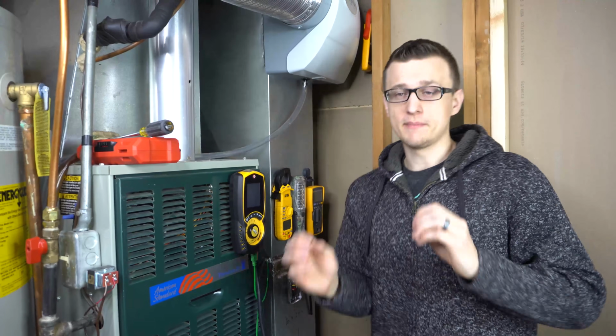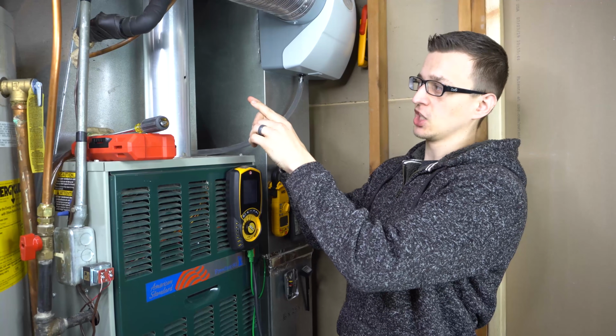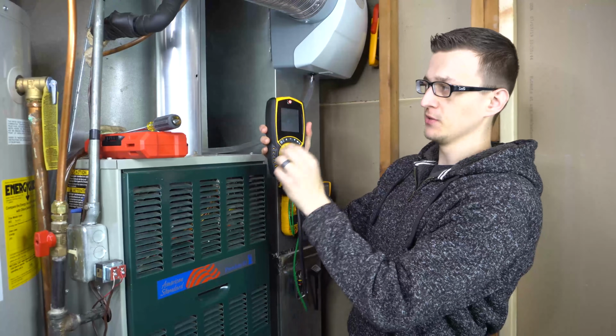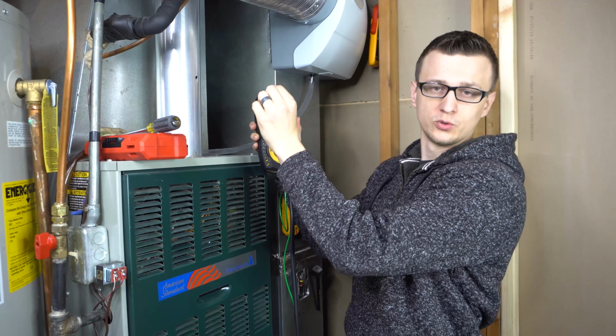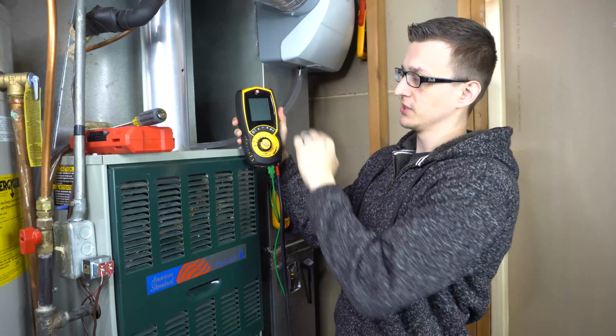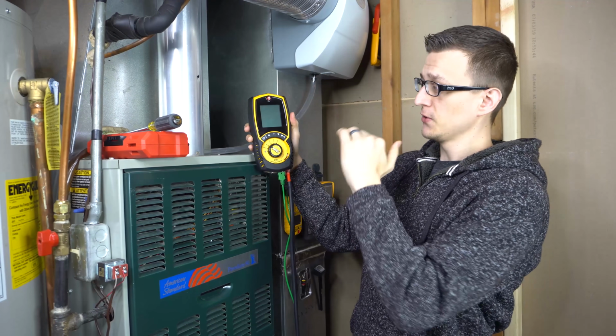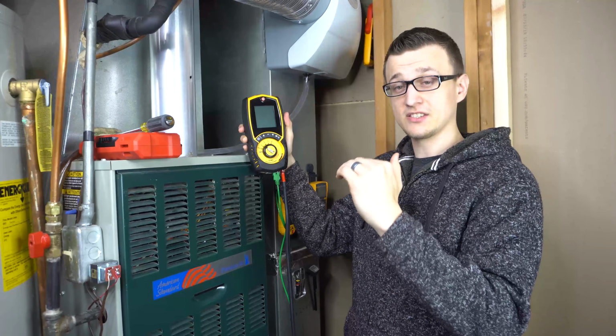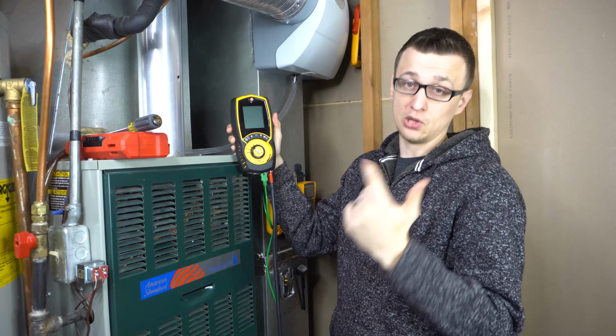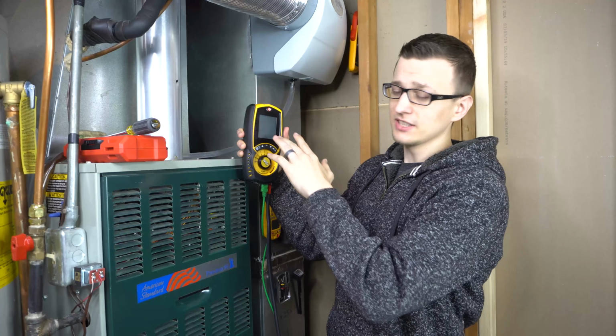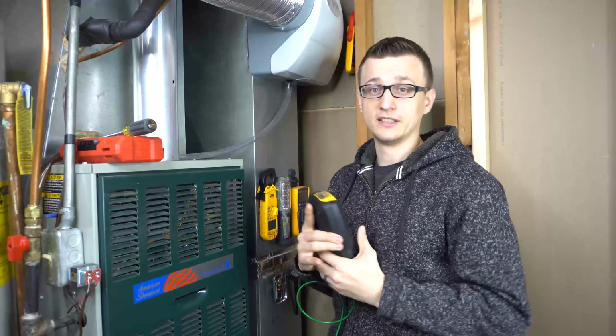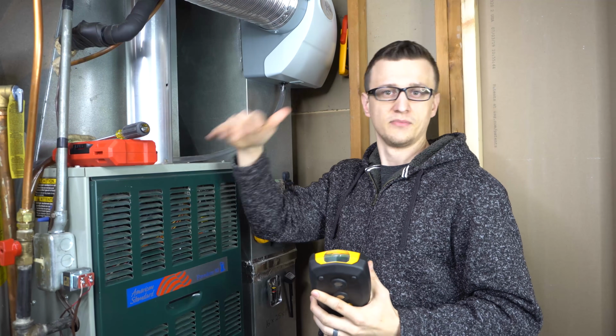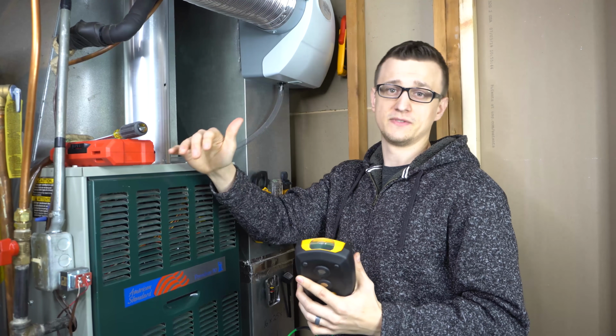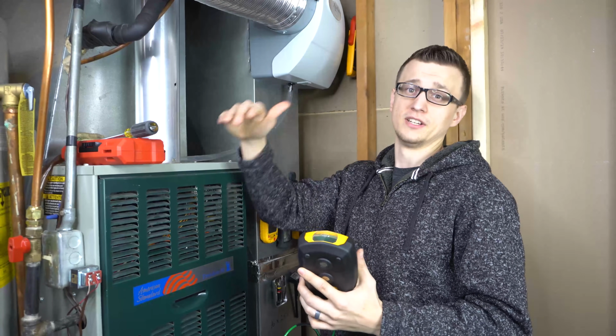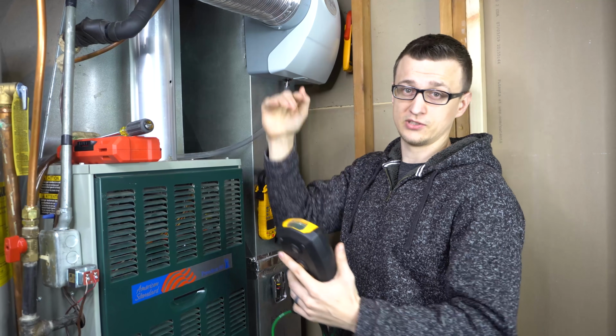Now, one more thing I want to mention is that when you're checking the carbon monoxide, really pay attention when you just stick your probe into the flue pipe. Really pay attention to the CO levels and see what they're doing. If you see the CO levels going up really fast, if you have a cracked heat exchanger or a plugged secondary heat exchanger, you're going to see your CO levels just skyrocketing. So it'll go from 5, 30, 90, 150, 300, 500.